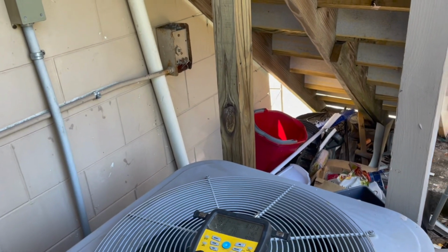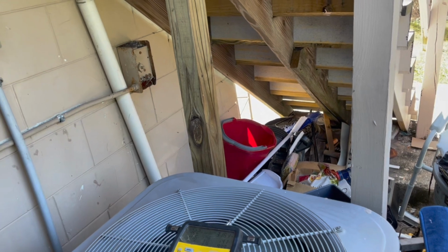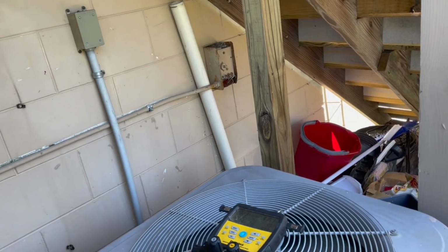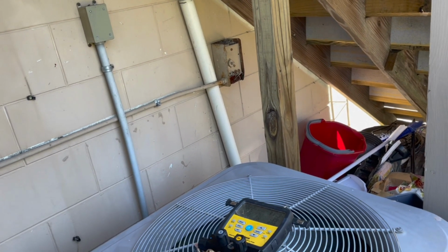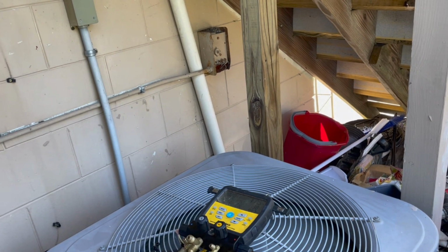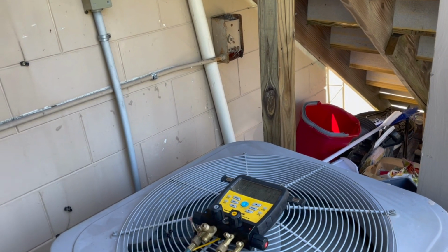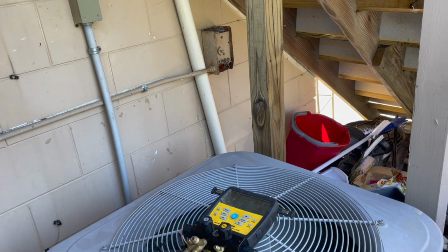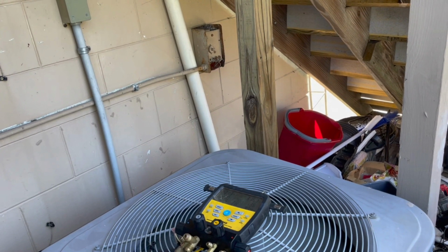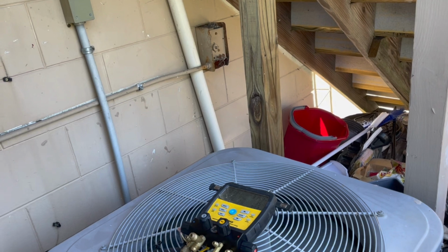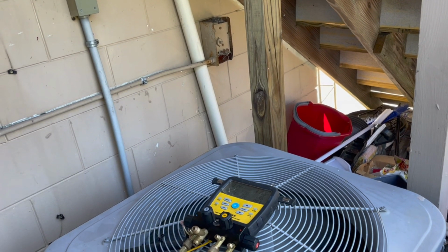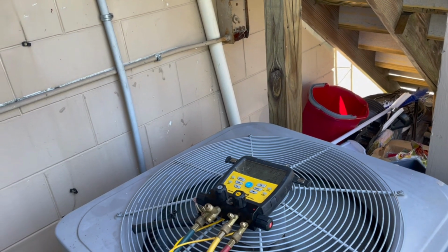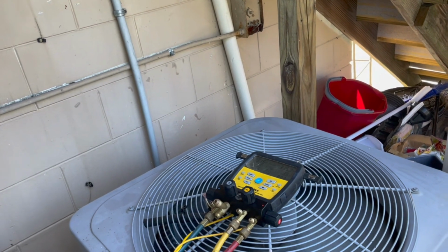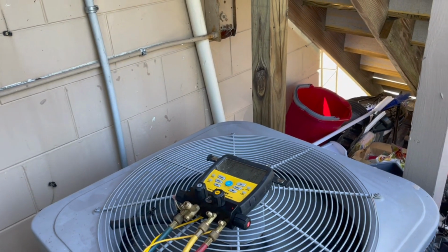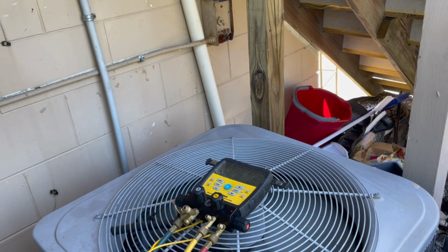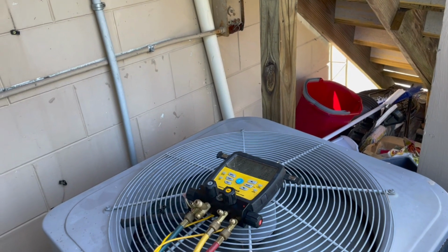If my low side doesn't come up, then I'll head inside. I'll see if maybe he's got an expansion valve, or maybe he's got a piston. Maybe someone changed out the coil and didn't put an expansion valve back in. If it doesn't look like it's a metering device issue, then maybe I'll look at airflow. I know the coil looks clean. There was a filthy filter in the return grill, but I took that out. So I'll just sit here and watch it for a bit. If it doesn't come up to a good level, then I'll head inside and start looking at the indoor unit to see what might be causing this.